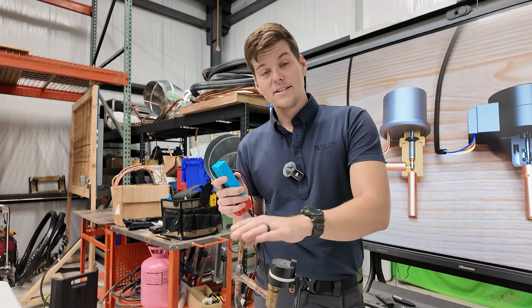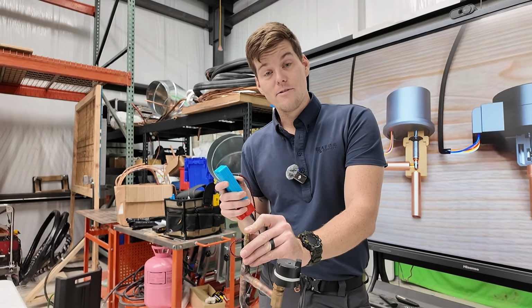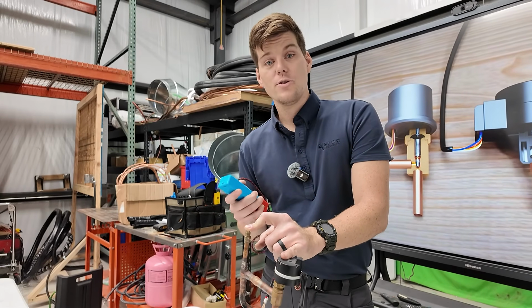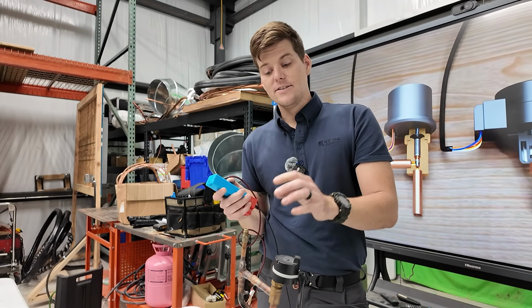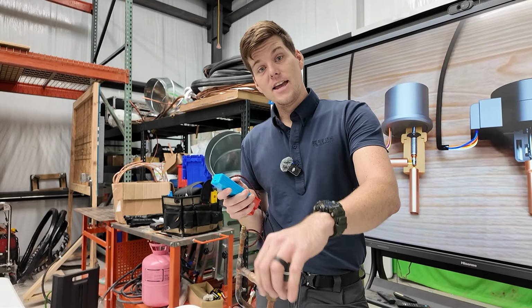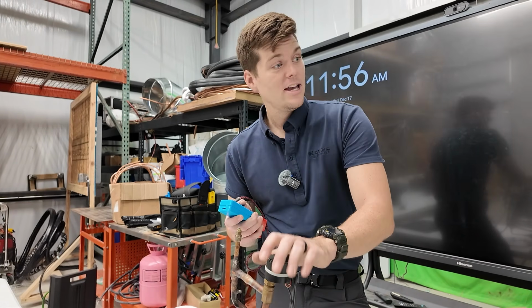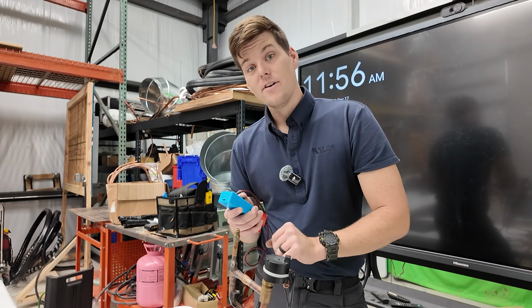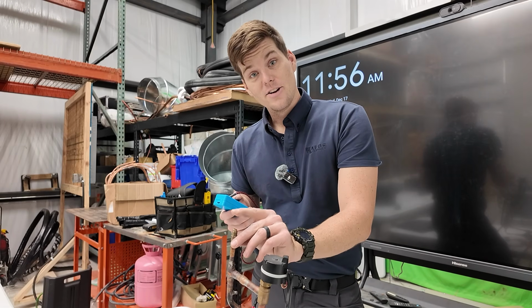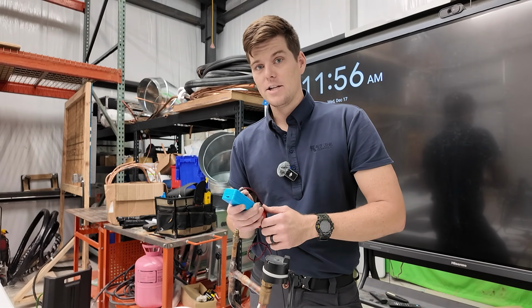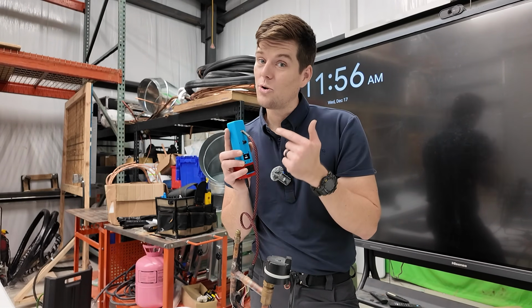Now remember, this is designed to stop those bleeds, stop that refrigerant from flowing into the coil when the unit is off or supposed to be off. It's a device that's allowed me to say that yes, this expansion valve works electrically and also this valve has failed internally because you can hear it leaking by. I'm going to recommend replacement. But I was able to test that because I had a tool like this.